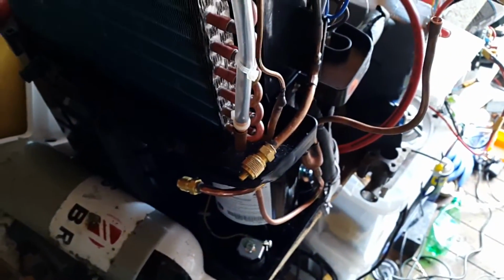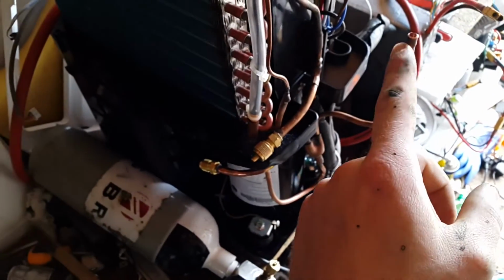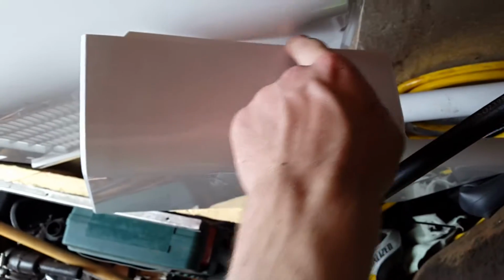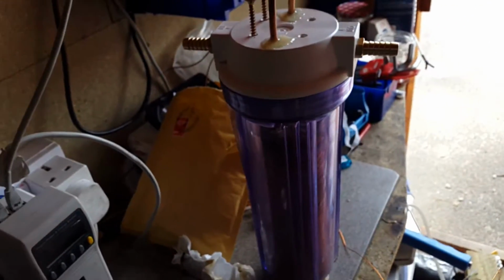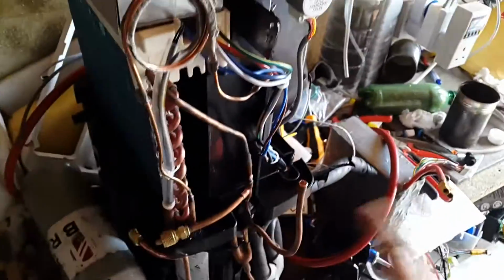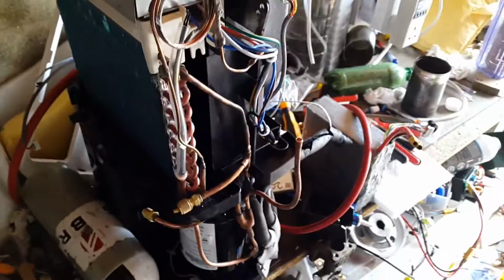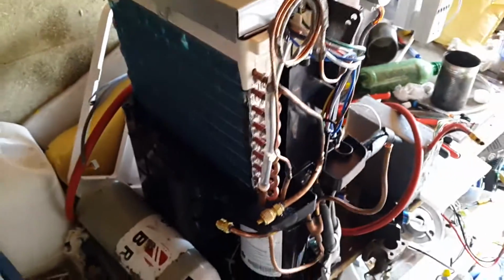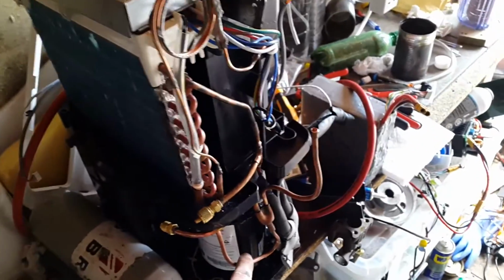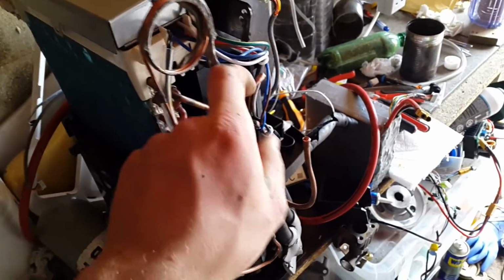And basically here's the discharge here, that'll be coming outside the casing. Where the two cases join, I'll just have holes drilled. And this is the new condenser here, which will be water cooled. And that will just be stuck right on the side of the unit. All I need to do is install the filter dryer and solder it all together.